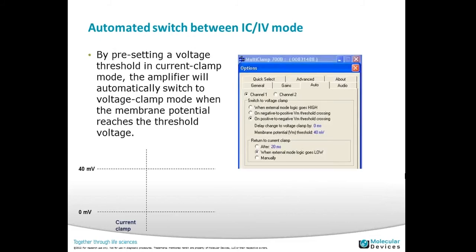Like I said, I like 700B because it has automated switching between current clamp and voltage clamp. For example, you can set it up so that under current clamp, once the membrane potential reaches a threshold like 40 millivolts, it will switch to voltage clamp. As shown in this example, once the voltage reaches 40 millivolts, it automatically switches to voltage clamp, allowing you to record the current.